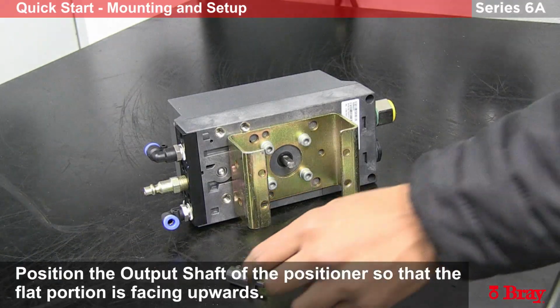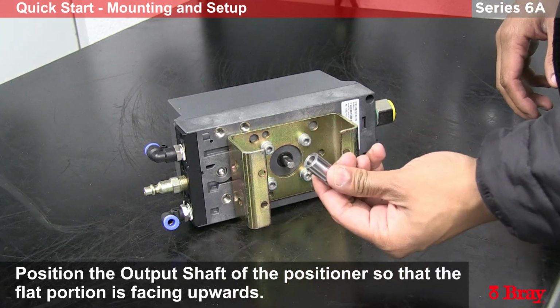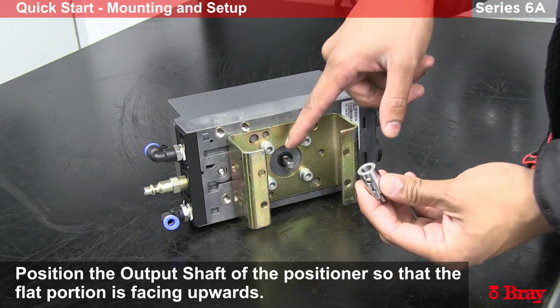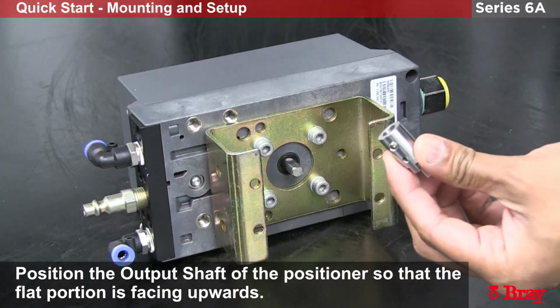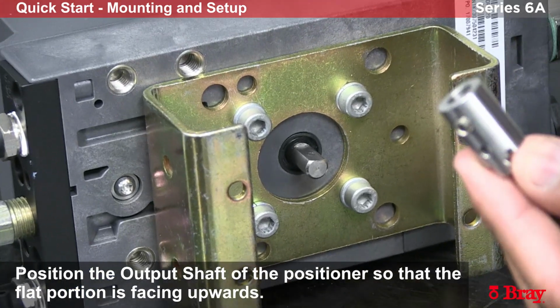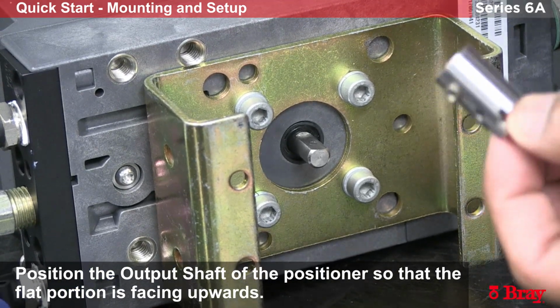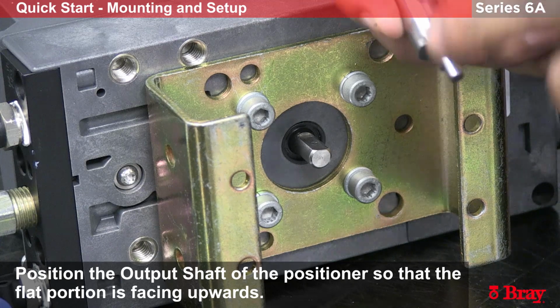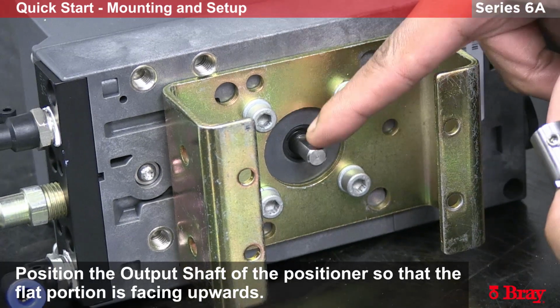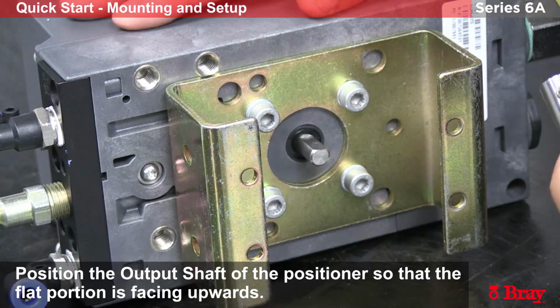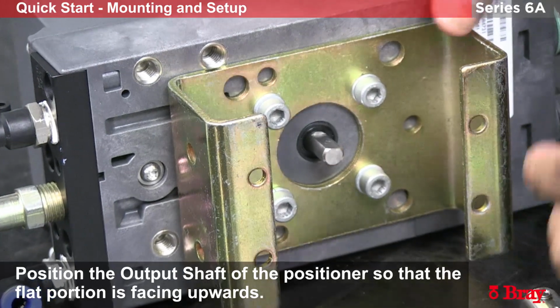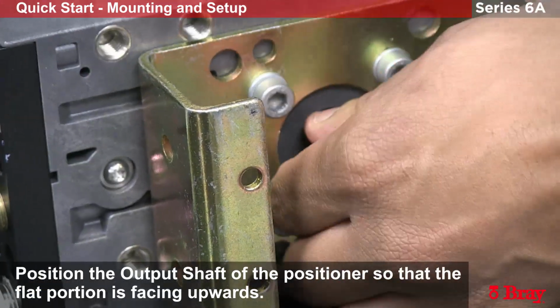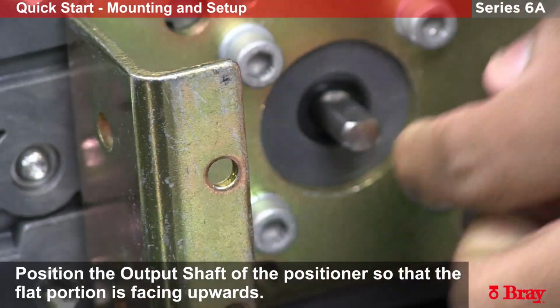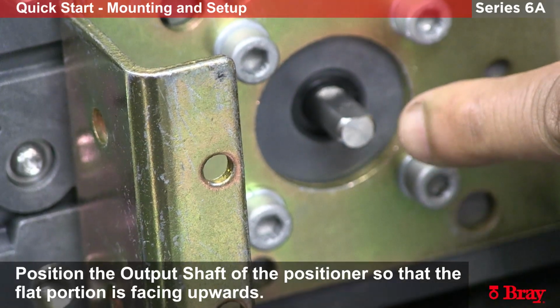Alright, our next step is to add the indicator shaft coupler. This coupler links the shaft of the 6A onto the shaft of the rack and pinion actuator. To do this, we need to make sure that the lock nut locks onto the flat of the shaft coming out of the 6A positioner. What we're going to do is rotate the shaft of the 6A to where the flat is pointed upwards.